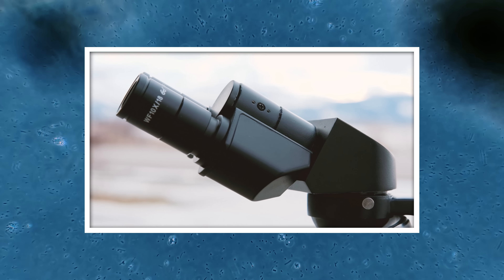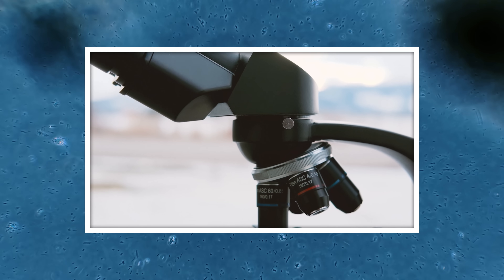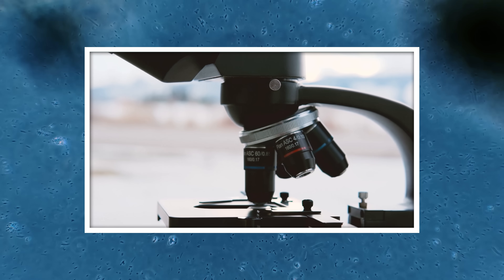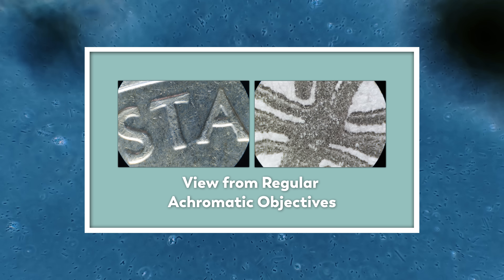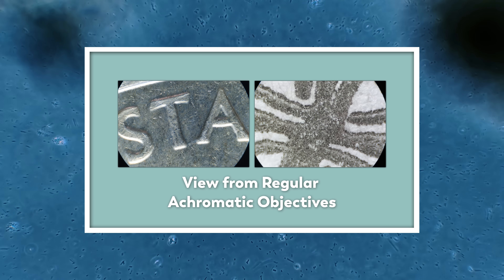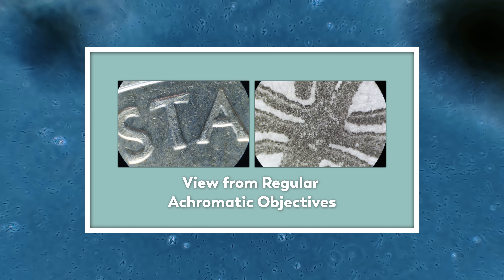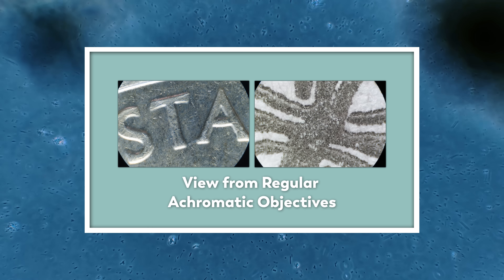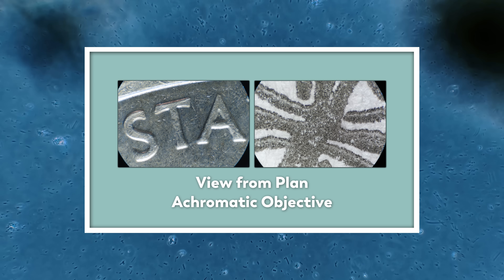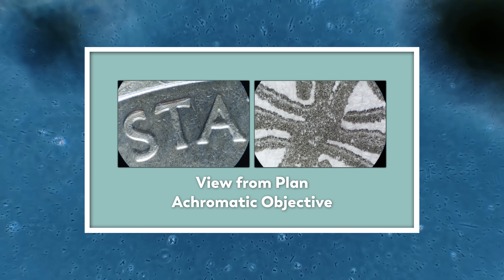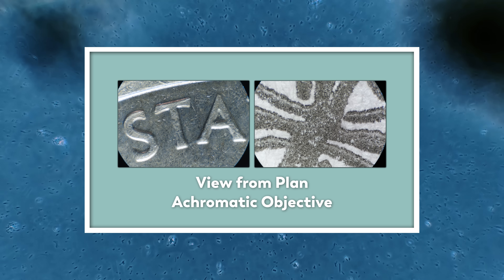These objectives don't just work on the microcosmos microscope — they will work on other DIN standard compound microscopes. Because of the way lenses are made, regular achromatic objectives display a curved image, which results in the edges of the field being slightly distorted and out of focus. But these plan objectives produce a flatter image across the entire field of view, resulting in an overall sharper image.